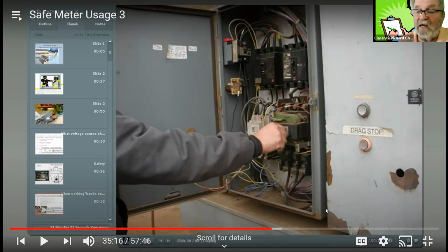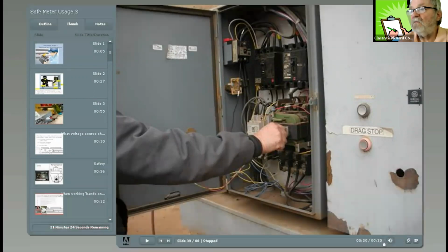Or if you're working in there and you drop a screwdriver across something by accident, that can cause this kind of thing. But the purpose of that motor starter is that it's an electromagnet to do this remotely, to close that switch from a remote point. Here he is doing it right up front. And if something goes wrong, he too is going to look like me about 50 years ago. Voltage with a high current short, and you can get a big bang.